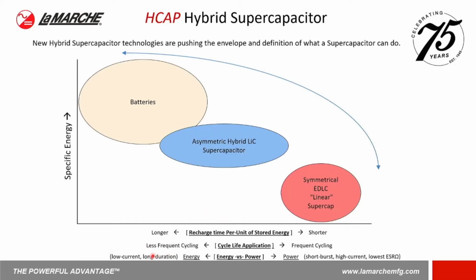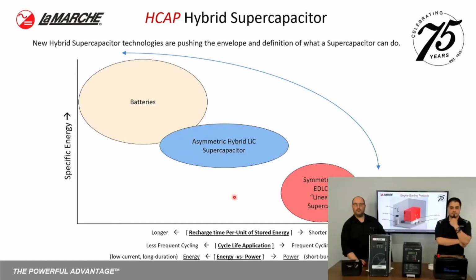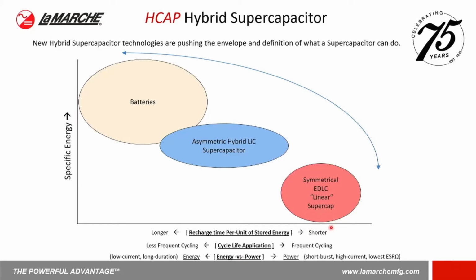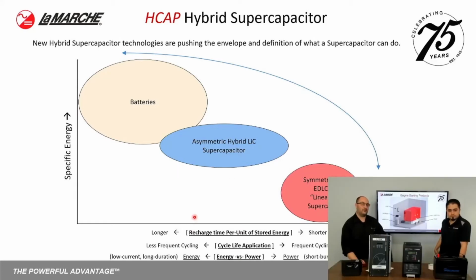Where if we look at it in terms of cycle life application, if you have tons of very, very frequent cycles, EDLC fits, but a lead acid battery does not. The asymmetric hybrid kind of crosses this boundary where you can get quite a bit of cycling performance out of it. And it's similar to a lead acid battery where you can increase the cycle life by using shallow discharges. You can have the same kind of improvements on an asymmetric lithium-ion supercap such as our H-cap. Also, in terms of energy versus power, the EDLC is going to win the power density, where lead acid batteries is not. And the asymmetric supercap kind of falls in the middle.